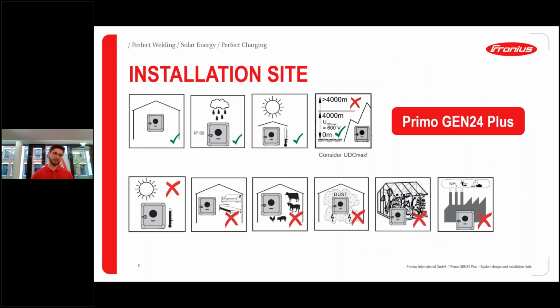Regarding the installation site, I have also put out a few screenshots. So we can see indoor is no problem, outdoor is no problem with our IP66 class. And please make sure to have a cover over the inverter if you install it outdoors, so there is no direct sunlight on it, as already mentioned. And also regarding the altitude, above 4,000 meters, it's no good to install, but until 4,000 meters, no problem. In the bottom line, we can see the direct sunlight.